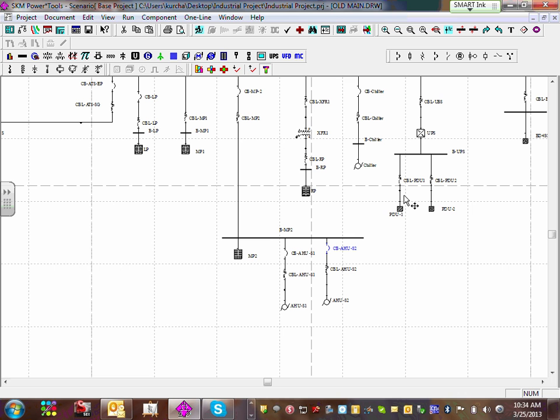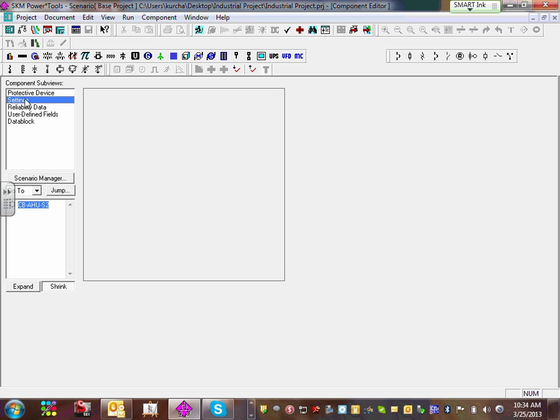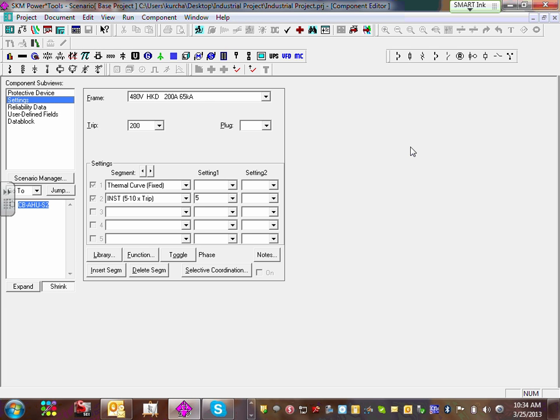What was our trip on the HKD? For that particular one, we tripped at, here's the settings which it already fixed, we set it up at 200. Here's how you adjust it, right from here you can pick your amps. So if you can see, the top will adjust the frame, and the bottom will adjust the plug and the trip, depending what type of circuit breaker you have.